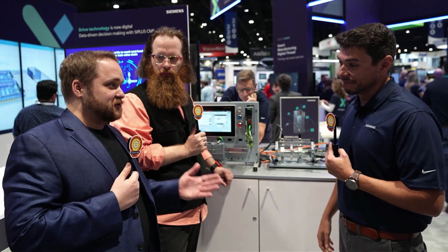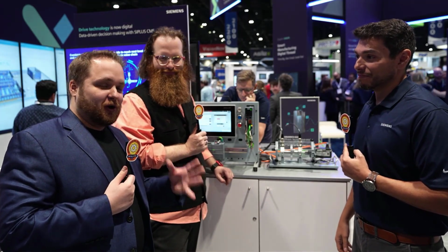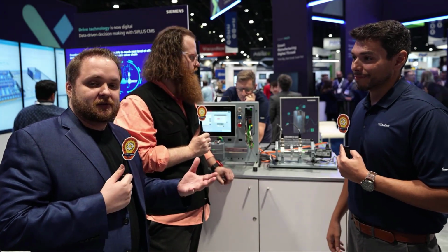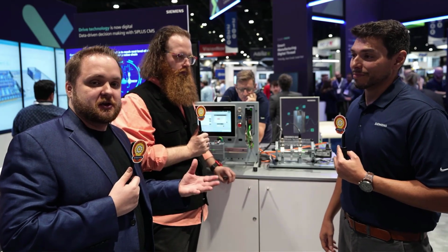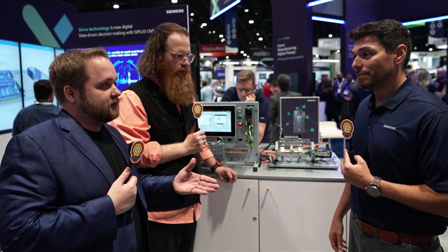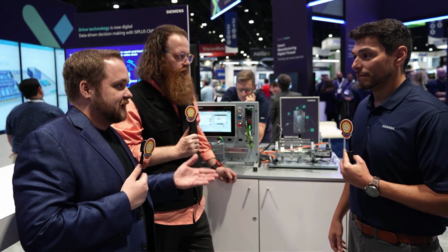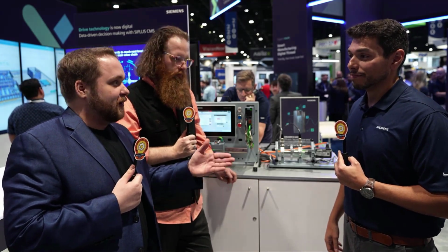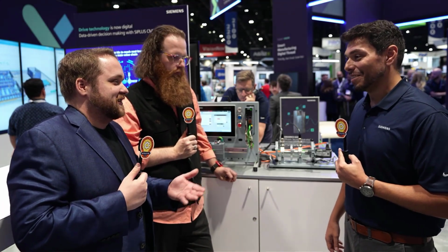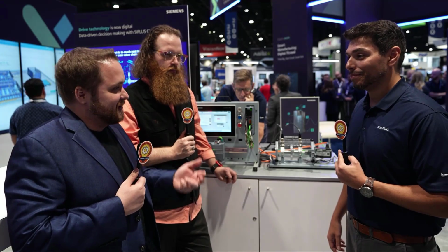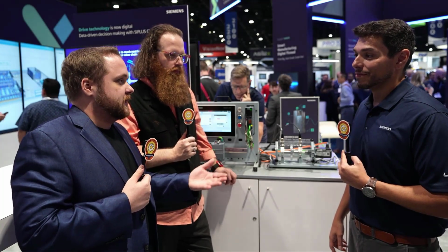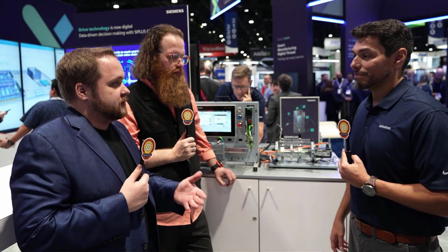Yeah, and I think that's extremely important, right? And I don't want to assume that all of our listeners necessarily understand drivetrains to the level that we're discussing here, but in a practical sense, I think the takeaway is if you have an issue in the drivetrain, it could be for a number of reasons, as you mentioned, and ultimately you want to save time in understanding where to look first, from a statistical analysis versus just replacing one part after the other, as you'll see very often in current environments, right? That is just the nature of the business. I think we've all been through that exercise. You replace the drive, you replace the motor, you replace the bearing, right? So here you can predict a little bit better what the issue is before taking that action, which is ultimately saving you dollars in downtime.